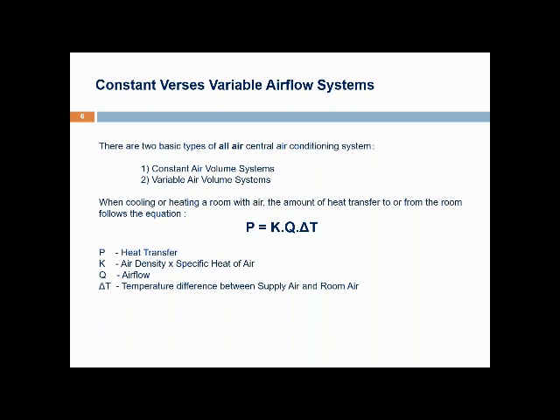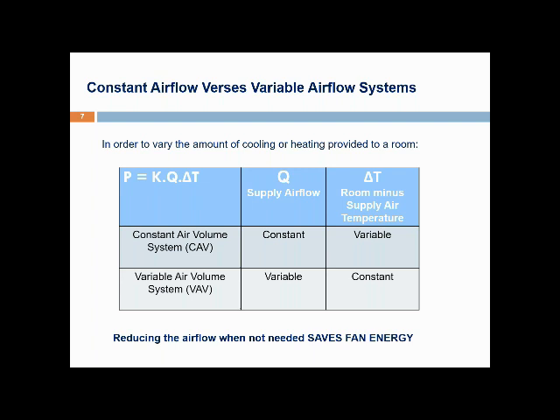VAV systems cool a building using only air and are known as an all-air system. There are two basic types of all-air system: the constant air volume system and the variable air volume system. Both cool the air by delivering it to the room at a lower temperature than the room temperature. The amount of cooling provided can be determined using the formula: heat transfer equals air density times specific heat of air times airflow times delta T — the difference between room and supply air temperature. These two systems vary the amount of cooling in two different ways.